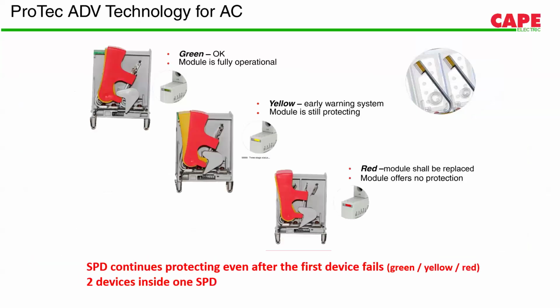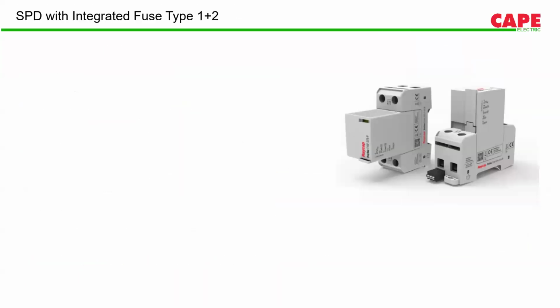Now, even after so much discussion, people are still confused about what rating of fuse we need to use. And another problem with fuses is they are bulky in nature. For example, there is an incomer rating of, let's say, 3200 amps or maybe 4000 amps. So at times you may need a fuse of up to 630 amps or 315 amps or 400 amps. In that case, the size of the fuse will be very high.